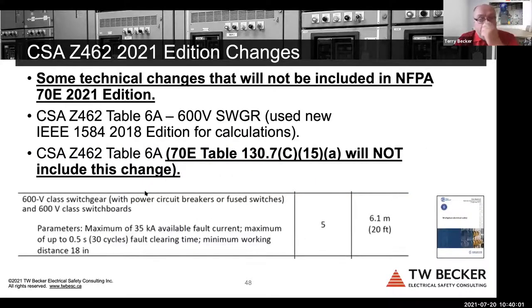So again, this is where we deviate. This is where the divergence is in Z462: the arc flash PPE category method in clause 4.3, or Article 130. We had the luxury of using the new IEEE 1584 formulas, and we had a working group redo the calculations using the parameters listed. And for low voltage switchgear, using these parameters, 35 kA and 30 cycles maximum available fault clearing time, it yields a far higher value than 40 calories. I think the number was 73 calories.